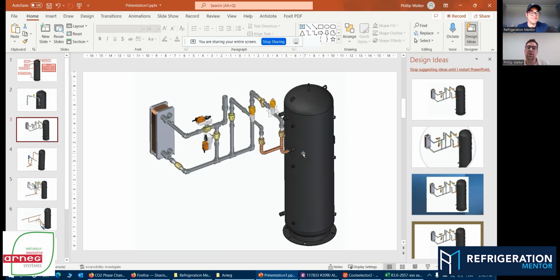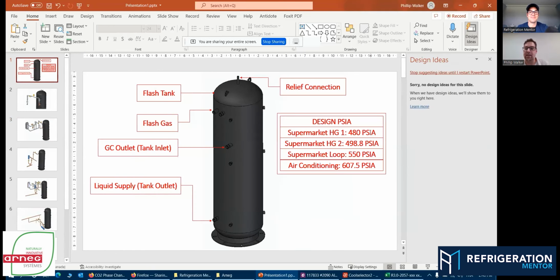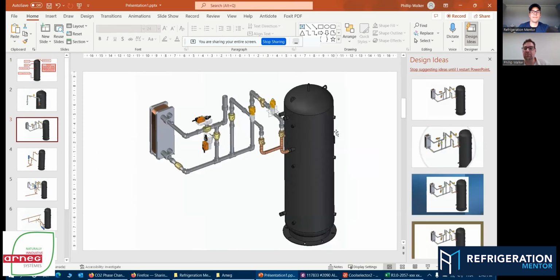And we're starting to diminish the effect of those delta or those pressures. I'm just going to skip back here, that we want to maintain. It becomes even more difficult to maintain that. So if we tack on hot gas defrost and all these other things at the same time, we start to lose that effect. So it goes back to, how are we going to create that, not only for a very hot environment, but how are we going to create it for a very cooled environment as well? I love it.